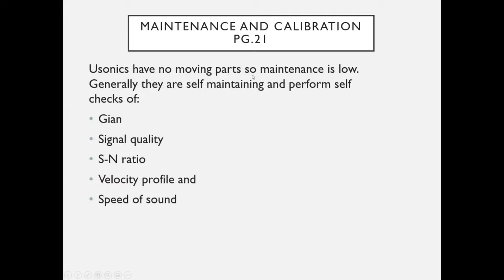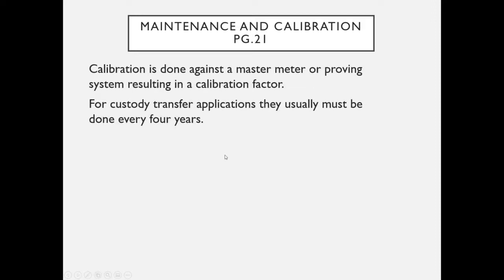Ultrasonic meters have no moving parts, so maintenance is relatively low. They are generally self-maintaining and capable of self-checks including signal gain, signal quality, signal-to-noise ratio, velocity profile, and speed of sound verification. Calibration is performed against a master meter or approved system, resulting in a calibration factor input into the transmitter. For custody transfer applications, calibration is typically required every four years, depending on application circumstances and applicable standards.